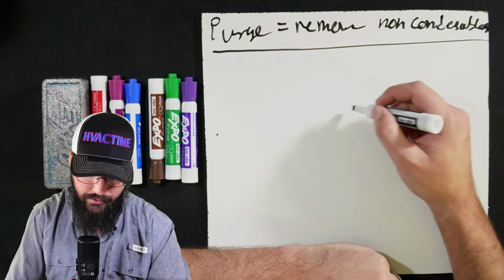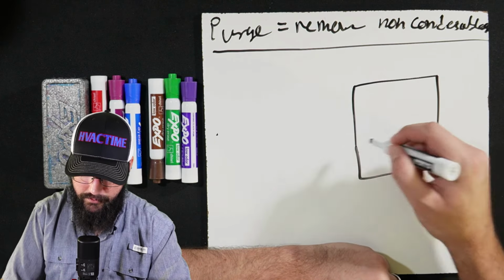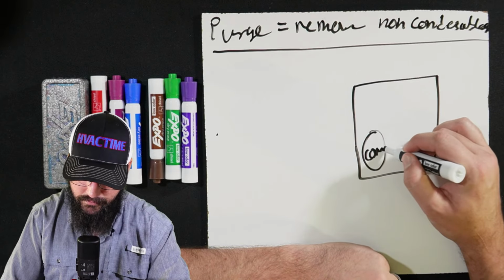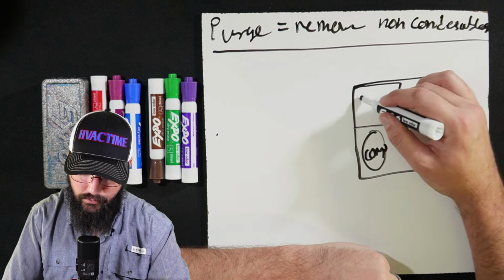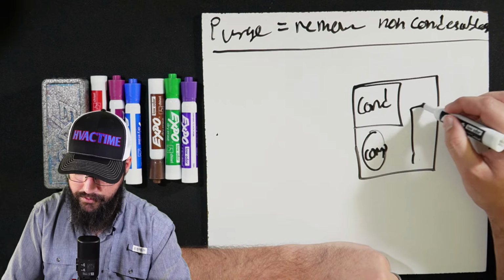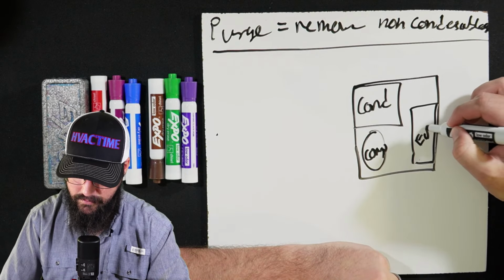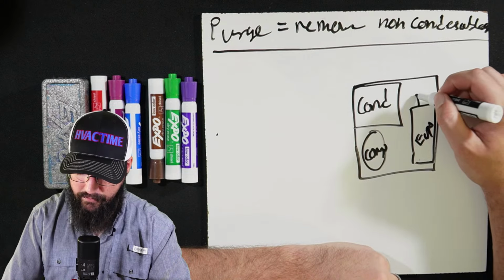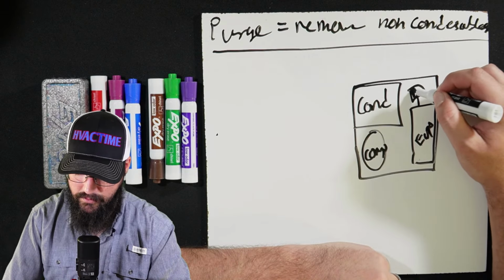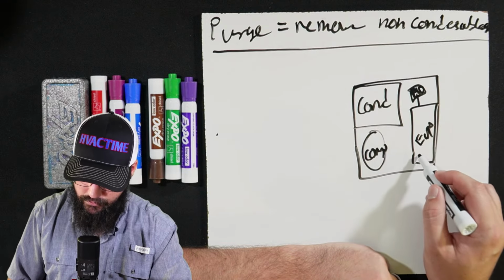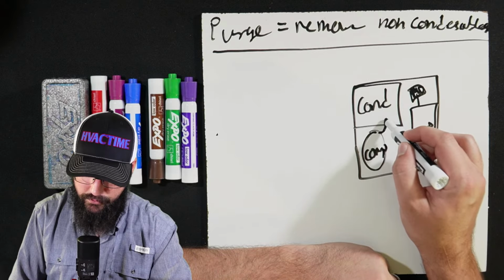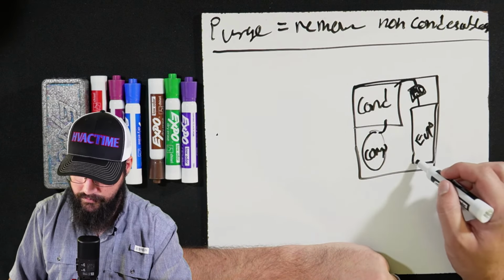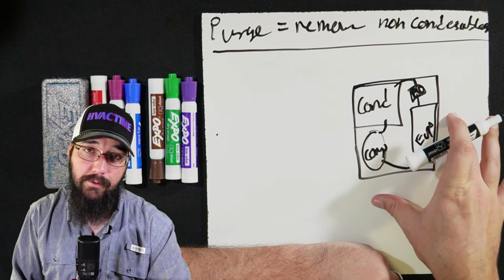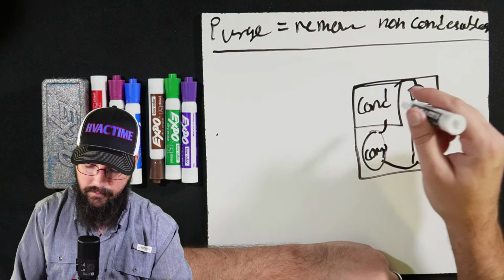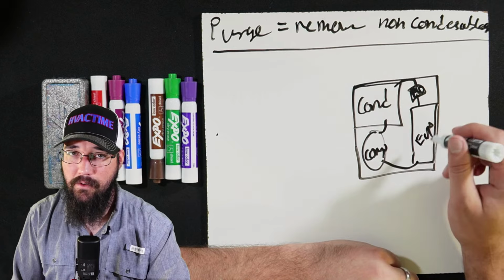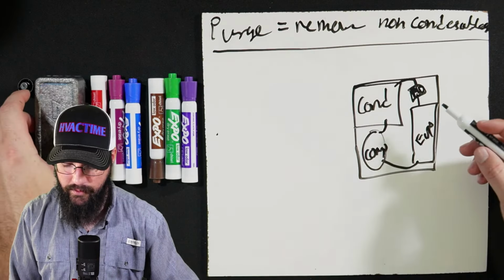Now, a purge is a dedicated little refrigeration unit. We've got a compressor. We've got a little condenser coil. And we've got the purge evap. This will have a metering device, MD, not that you can read that. And so the compressor goes into the condenser, feeds into the metering device, and then that's your basic refrigerant cycle. And this is completely independent of the chiller.